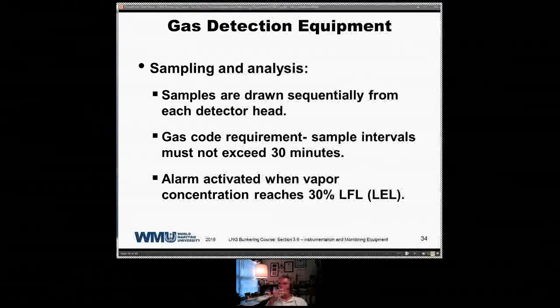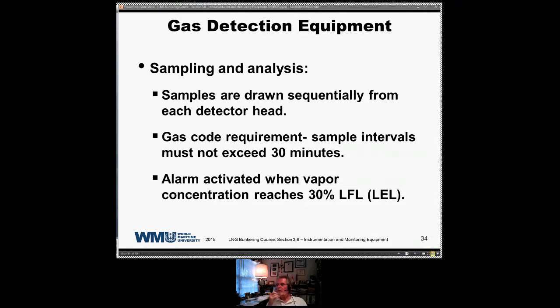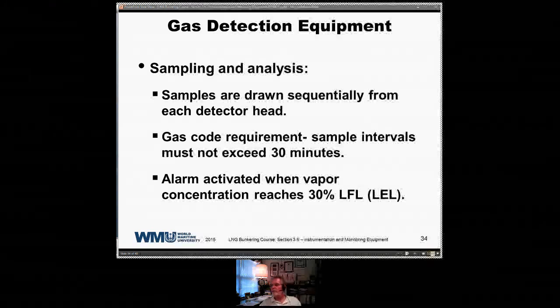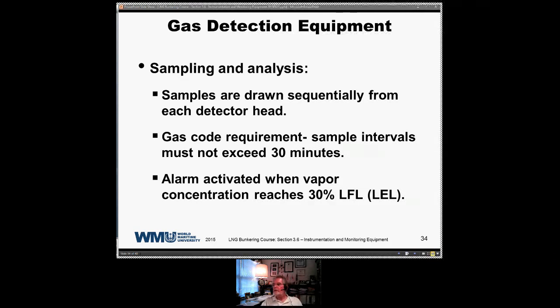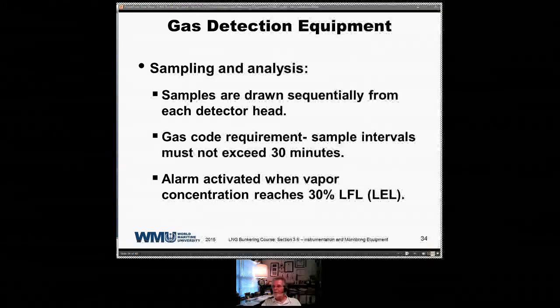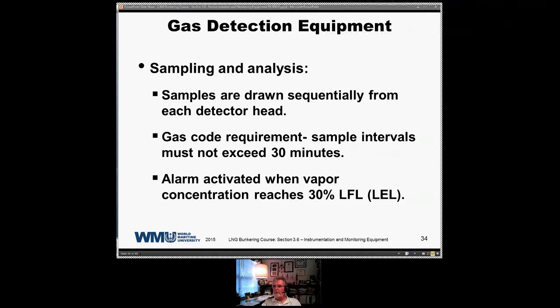Sampling and analysis: samples are drawn sequentially from each detector head. The gas code requirement is that sample intervals must not exceed 30 minutes. So as I said, once every 30 minutes, every space must be checked. And the alarm is activated when the vapor concentration reaches 30% of the LEL, the LFL, 30% of 5%, 1.5%. Don't get caught on these percentages here. Always bear in mind when you see these referred to, what are we talking about? The gas detector alarm is at 30% of LEL. LEL is 5%, so 30% of 5% is 1.5%.